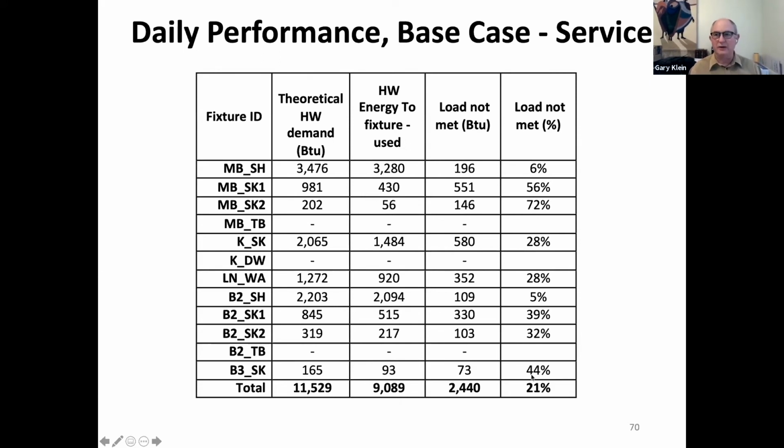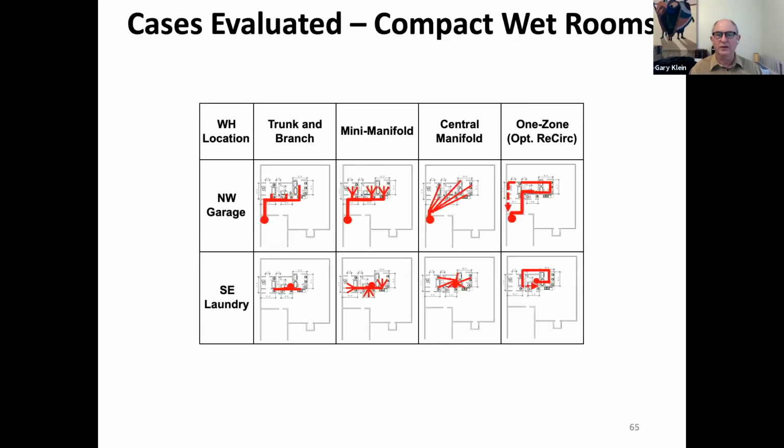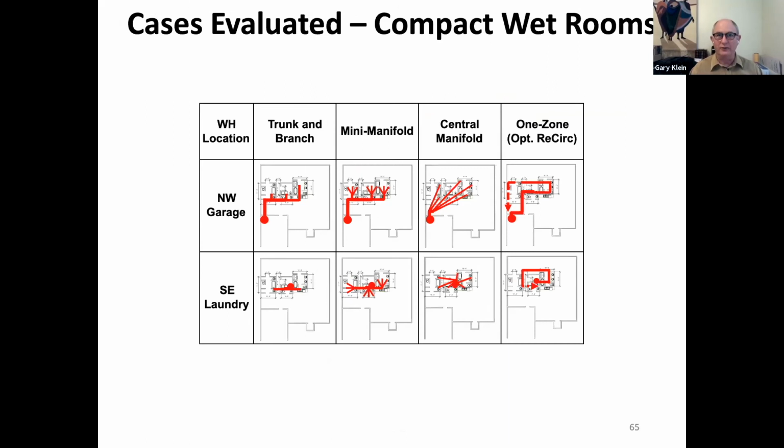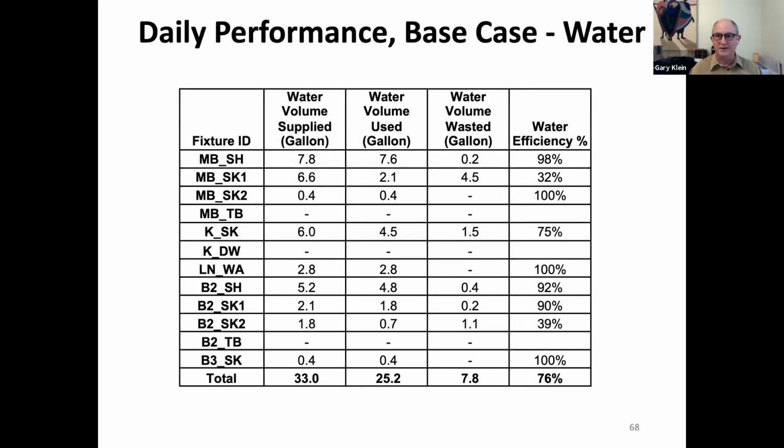We want to have similar levels of service no matter what we analyze. And I'm going to tell you that these methods are not the same level of service. Why? The source of hot water depends on which event is in which order and how far that event is from the trunk line. They're not the same. If we're going to analyze and compare things, we have to have the same level of service. Otherwise, we have fruit salad. I want apples to apples comparisons. I don't want fruit salad. I like fruit salad, but not for this analysis.